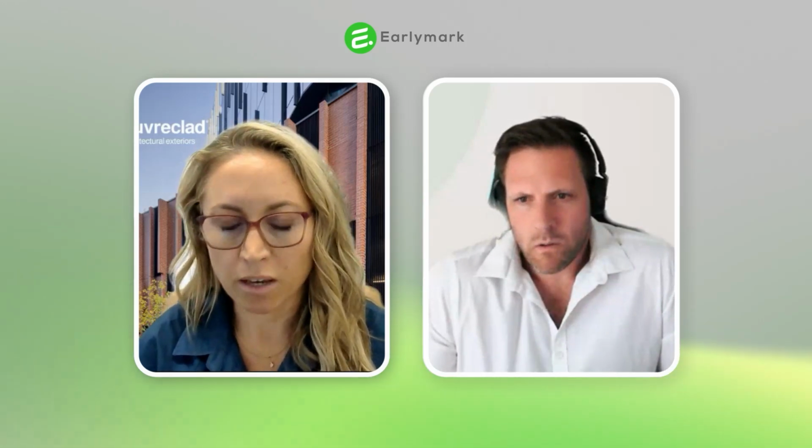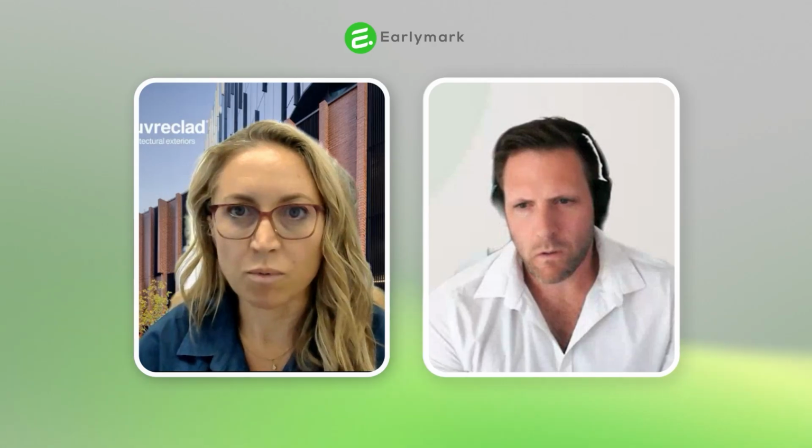Uddhava, let's start with the old AS 4740 2000 standard. It's been around for ages. What was wrong with it? Well, Michael, a few years ago when we were testing Louvres, we discovered that there was a lot of ambiguity in the standard. And this led to misinterpretation of how the test rig was set up, some of the instrumentation, and there was also a bit of ambiguity around the terminology, which was very critical to the calculations in this testing process. So that is where we started and realised that we really need to update the standard to really clarify what this testing process requires.